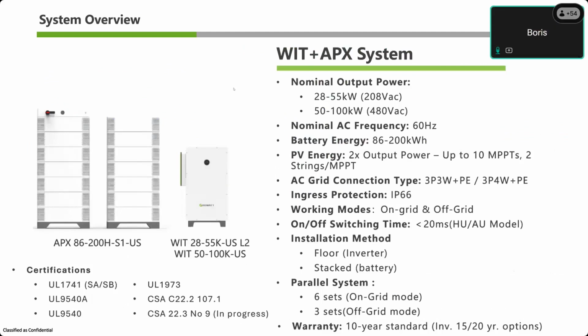Okay, I'll keep going. So with PV, the rule of thumb for our inverters is there's up to 2x PV versus output power. So for our 50 kilowatt inverter, it can process 100 kilowatts of solar. The only exception is our biggest inverter, the 100 kilowatt unit, which can only do 156 kilowatts of solar. Each unit has up to 10 MPPT inputs, 2 strings per MPPT.